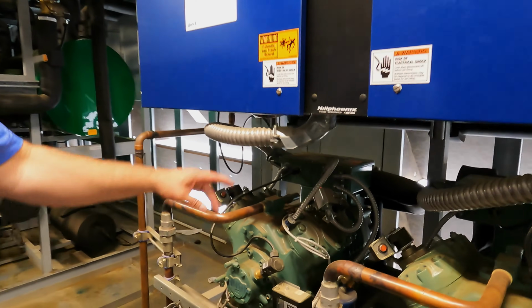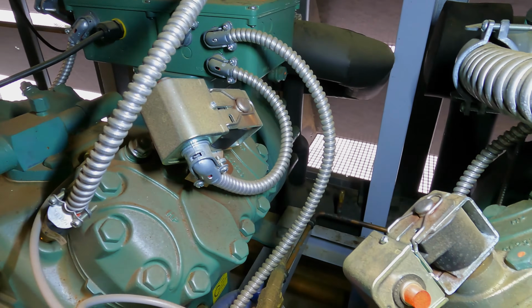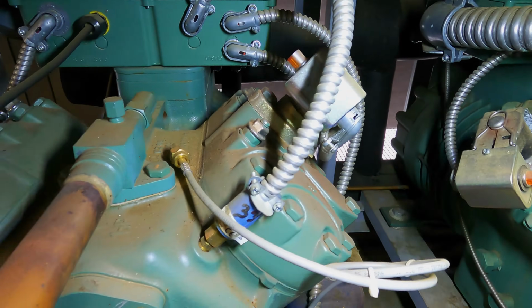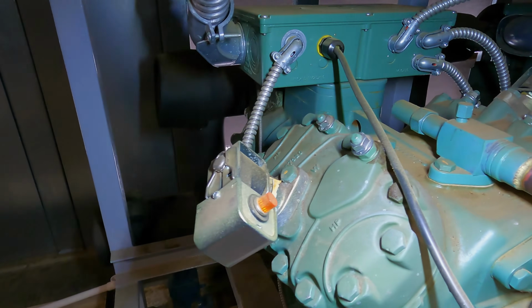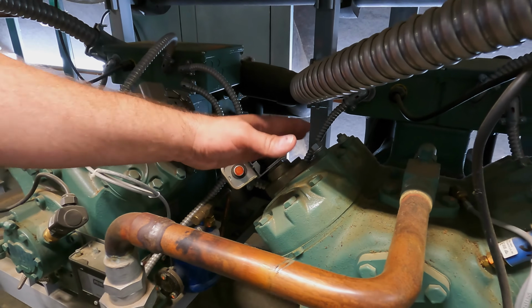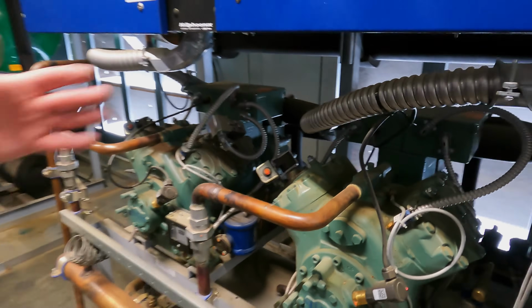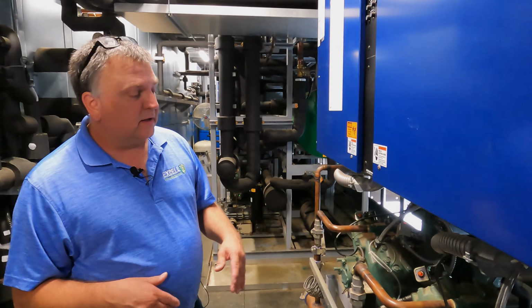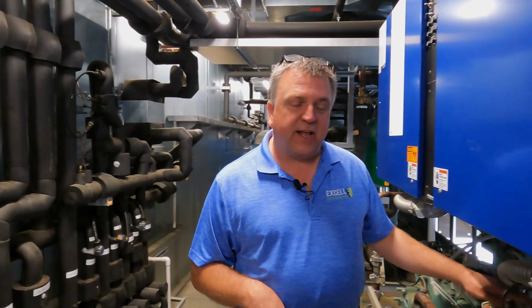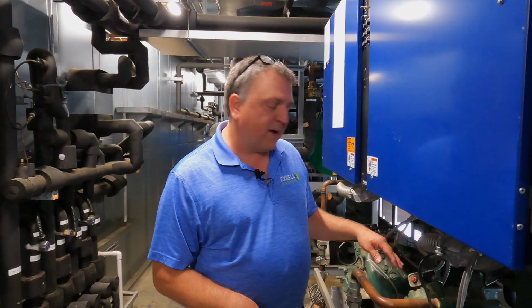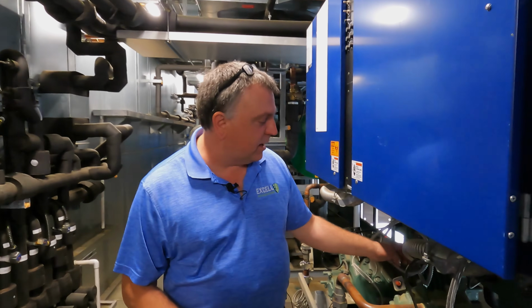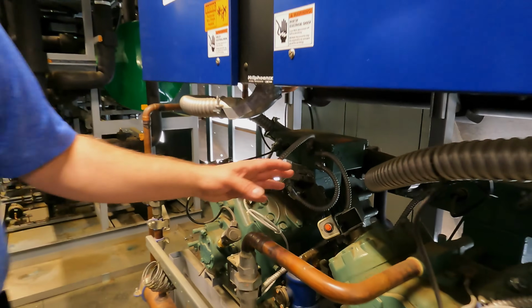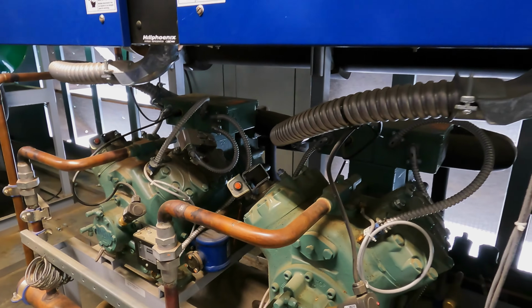On these compressors, we have what we call unloaders. Basically what this does is it shuts off this bank. So when this energizes, this will become a floating head. The cylinder's still running, but it's doing no work. Those valves open up and it just sits there. And you can actually see it on an amp meter. We'll probably pull 30 amps when we're fully loaded, and we'll probably pull about 15 to 18 amps when it goes unloaded. Unloaded means that's energized, that side's off, and we're just pumping that side.